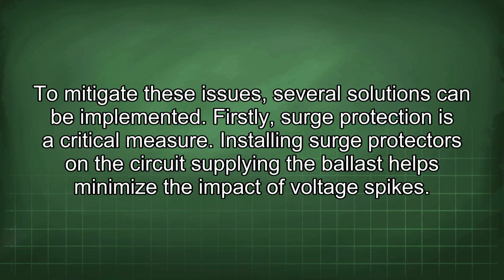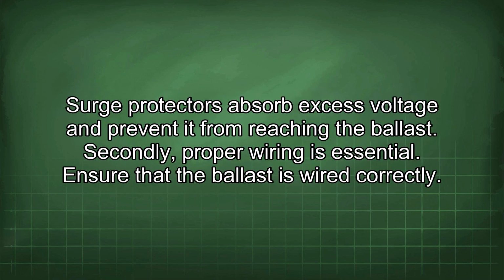To mitigate these issues, several solutions can be implemented. Firstly, surge protection is a critical measure. Installing surge protectors in the circuit supplying the ballast helps minimize the impact of voltage spikes. Surge protectors absorb excess voltage and prevent it from reaching the ballast.